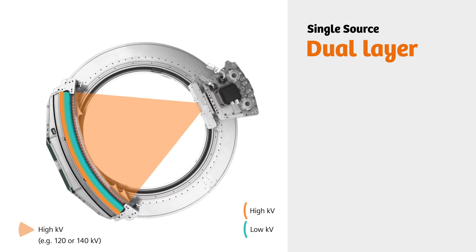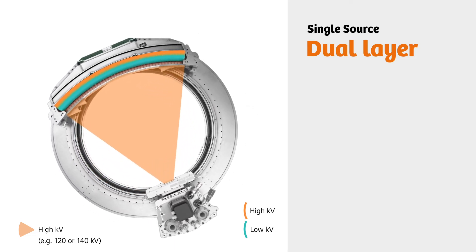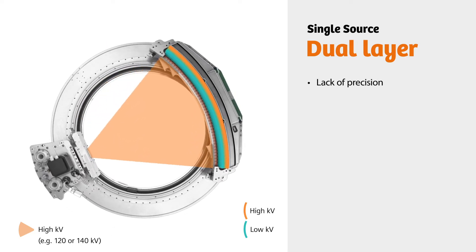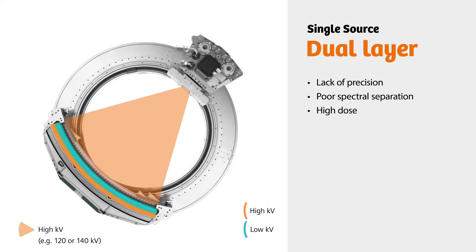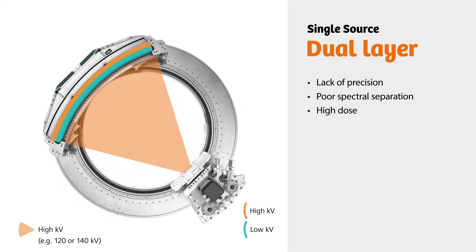Dual layer detectors enable faster scan speeds than KV switching. However, they are not precise enough to properly distinguish between high and low energy photons, and therefore suffer from poor spectral separation. The dose is also high, because dual layer detectors require fixed power settings and mAs quantities throughout the acquisition.